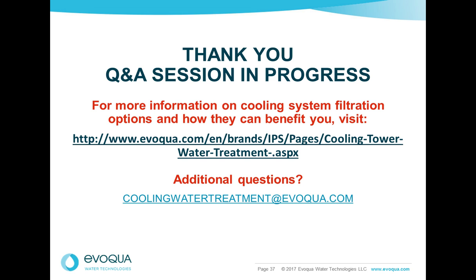Now, if I install a filter, how do I know that it's working properly and making any difference on my system? So, two ways. Visually, but visually is not a great way because you're only really seeing a small fraction of the system. Really, the best way is to do a particle size analysis before you install the filter as a baseline, and then run the particle size analysis again 60, 90 days after the filter has been installed, and compare results. And then maybe do it again annually after that. You also might see over time your chemical usage drop a little bit, your biocide use drop a little bit. That's going to be an indicator as well.